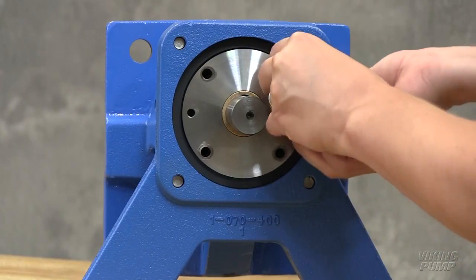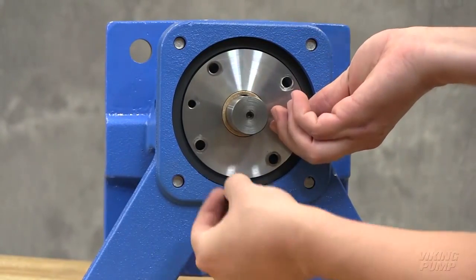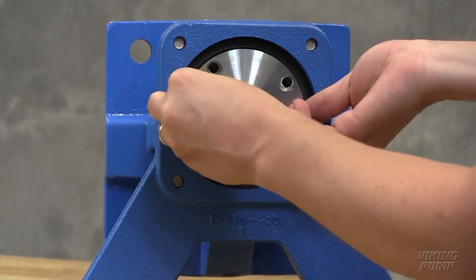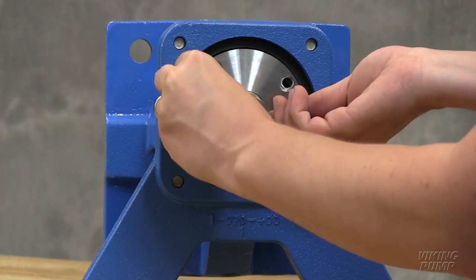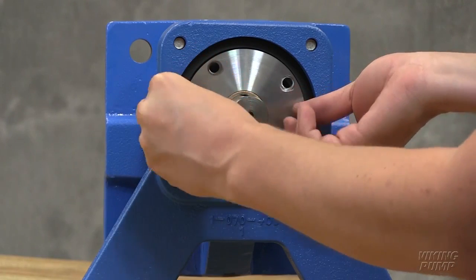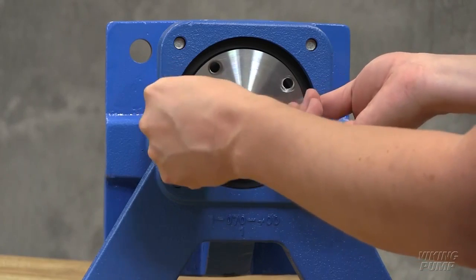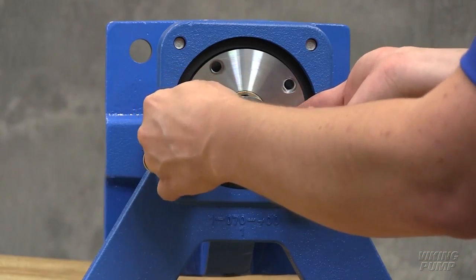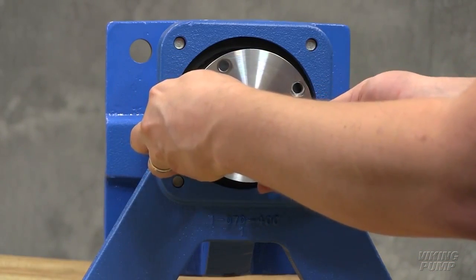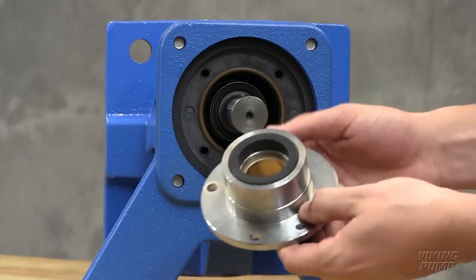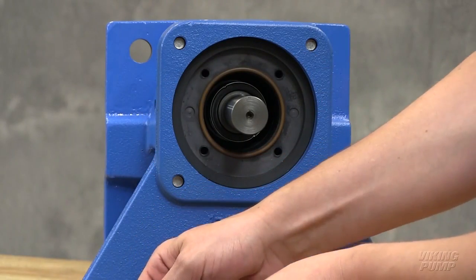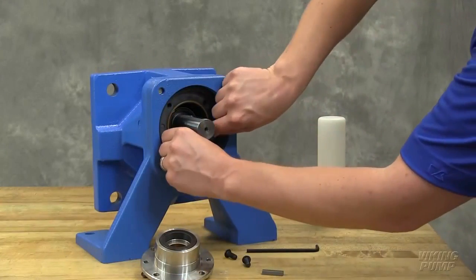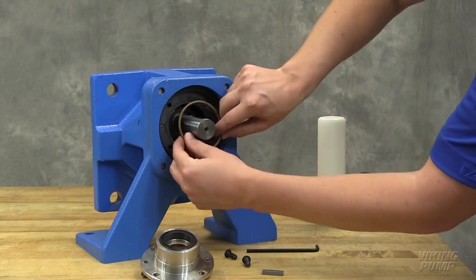Use 2 of these cap screws as jacking screws to remove the seal holder slowly from the pump bracket. Be careful when removing the seal holder from the bracket, as the carbon element of the rotating part of the seal will tend to stick to the stationary seat. When it does this, it can fall off at any time once the seal holder has been removed. Remove the O-ring, which seals the seal holder and bracket.